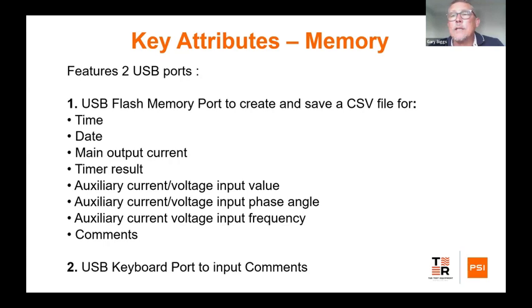So it means you're not tied to a software. You can use Excel or whatever you're wanting to use to read the CSV file. And when we store data, we're storing the time, the date, the main output current, the timer result, auxiliary voltage or current values, the current or voltage phase angle from the main channel, and the auxiliary current voltage input frequency. So whatever we've set that auxiliary metering, auxiliary output, whatever the frequency is set to, we will know what that is.